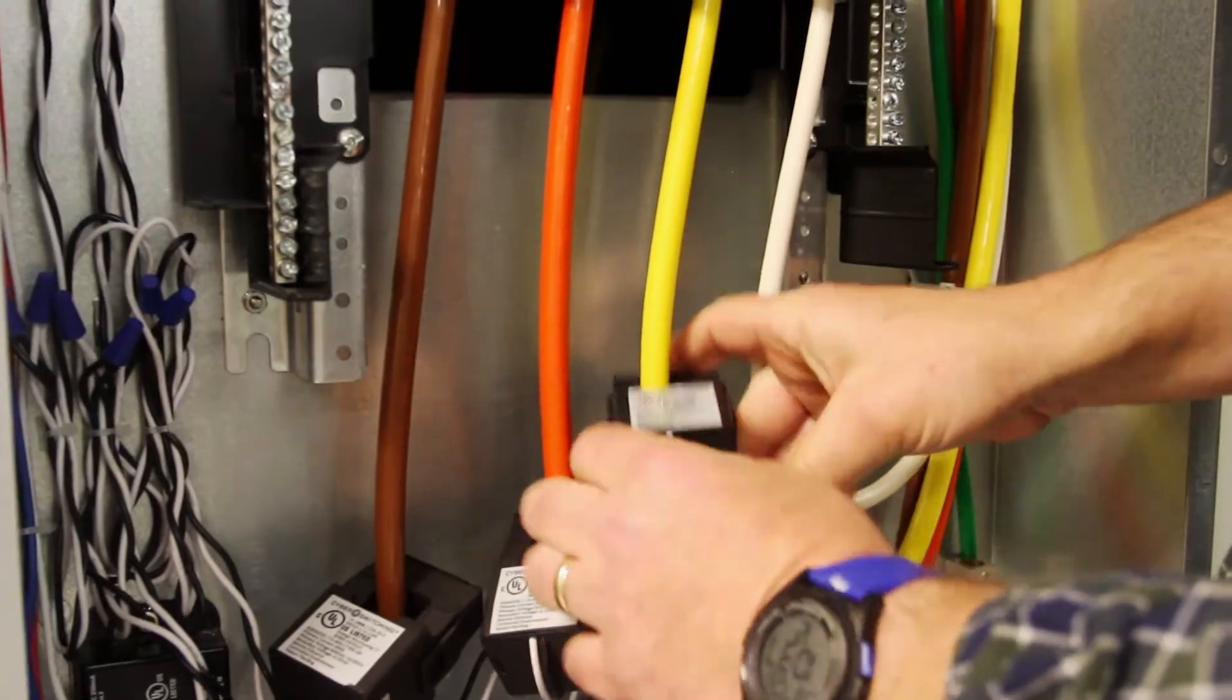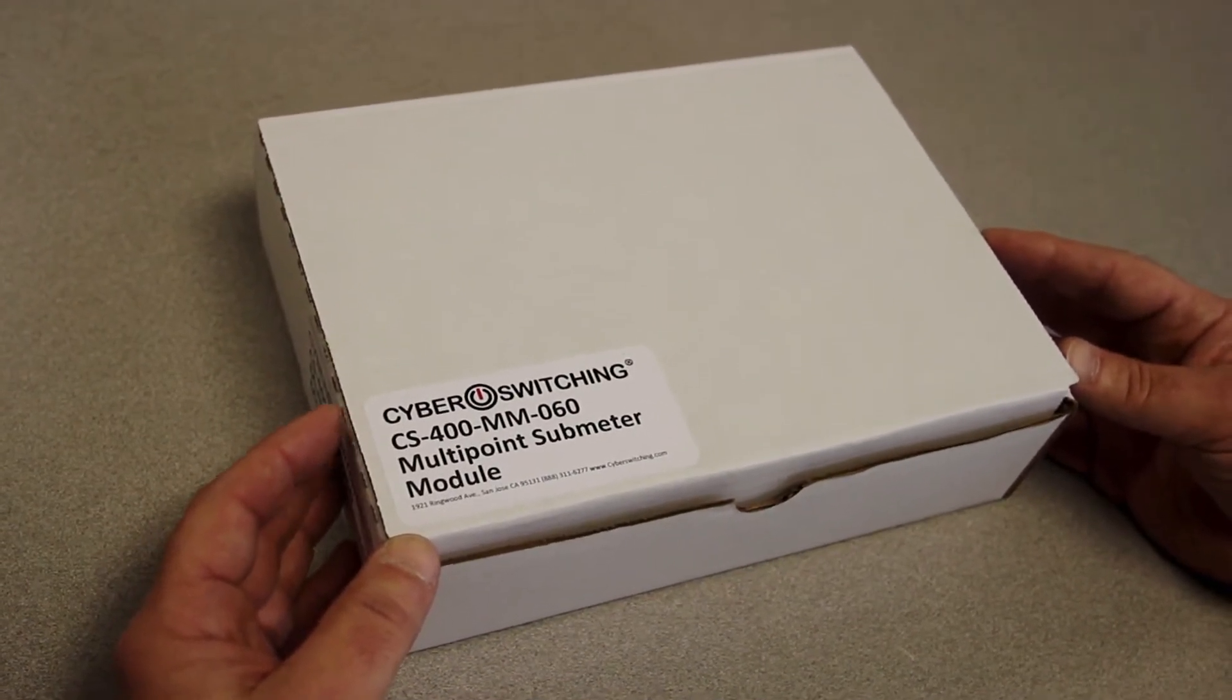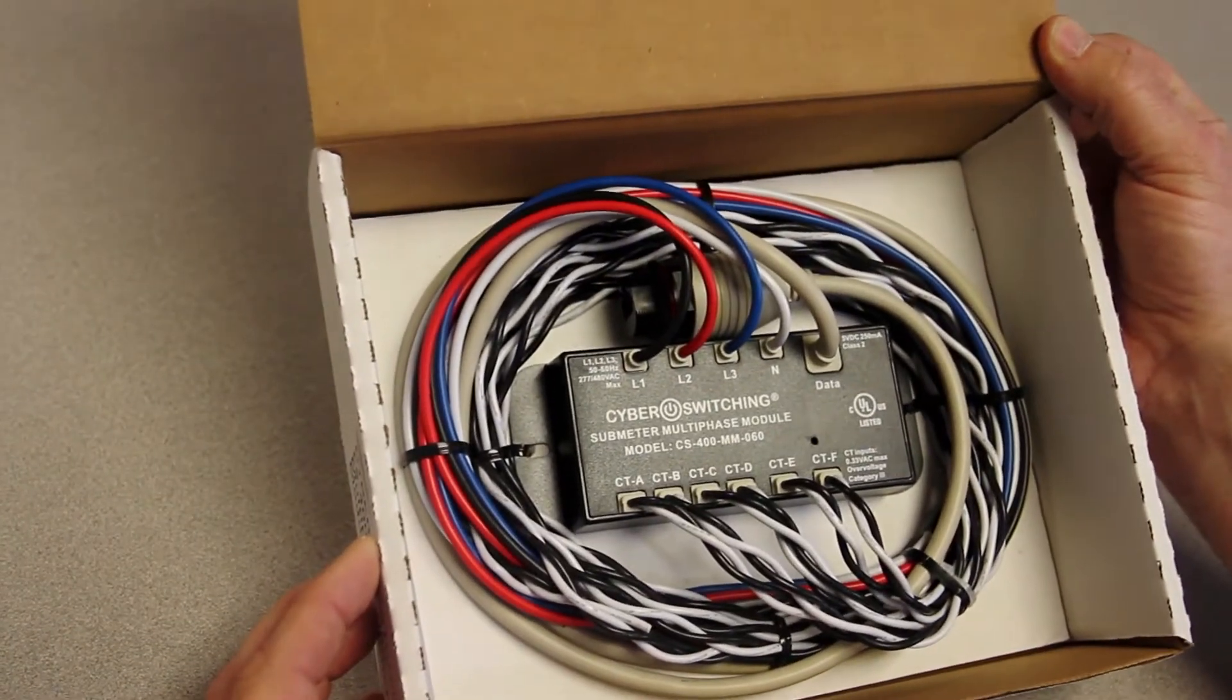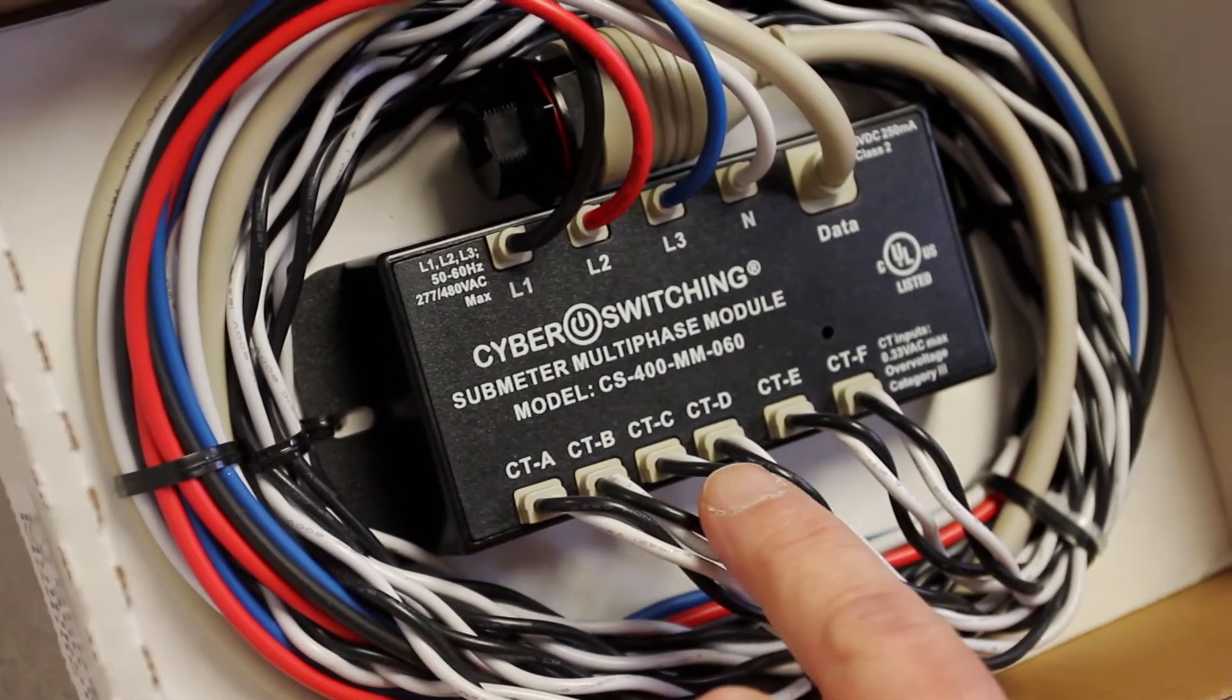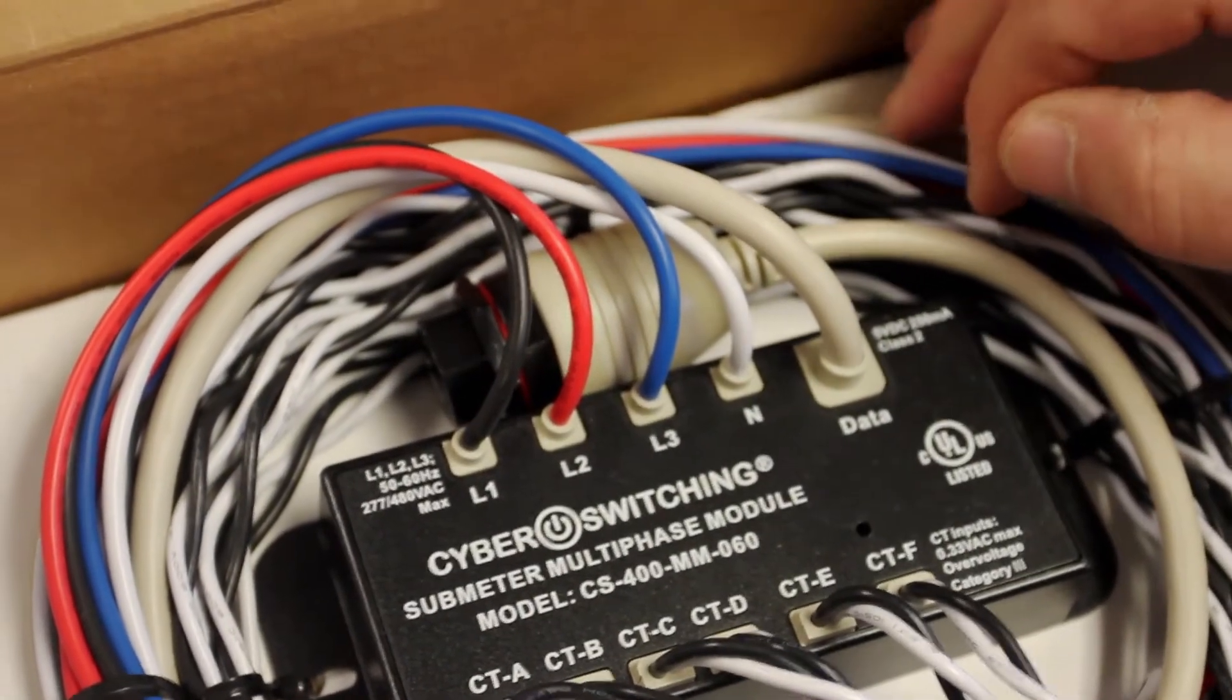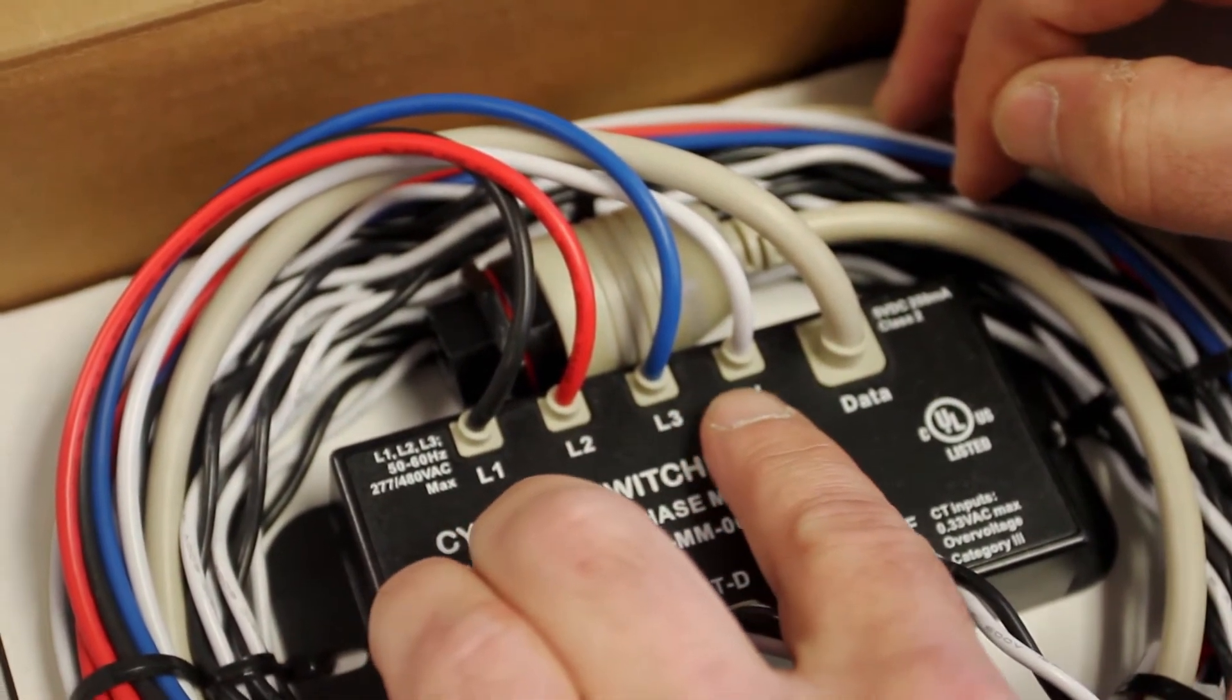Once installed, the coils will be connected to the CyberSwitching Multipoint Submeter Module. Each module can monitor up to six CT coils. The module has separate input lines for monitoring line voltage. Each input line connects to phase voltage at the breaker as needed.